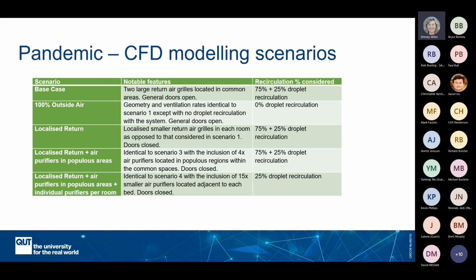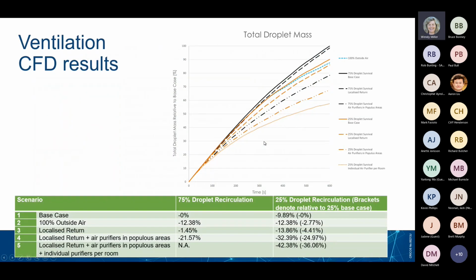And there is little scientific evidence about droplet circulation, recirculation, about how many droplets remain suspended and how far they travel and what their decay rate is in HVAC systems. So for this analysis, 3 droplet recirculation percentages were considered. For the 100% outside air, it was assumed that there was no droplet recirculation. For the others, the calculations were done assuming 25% recirculation or 75% recirculation.